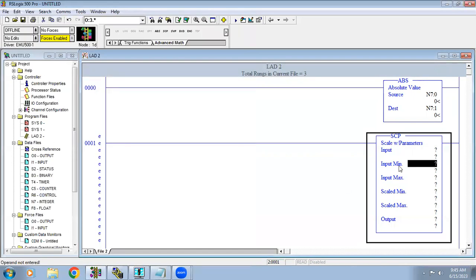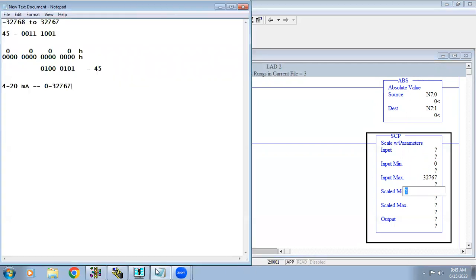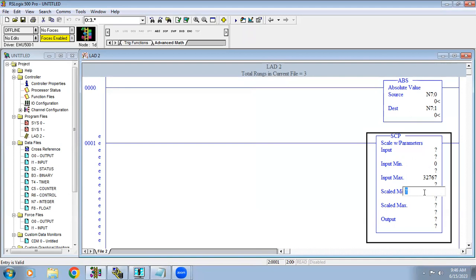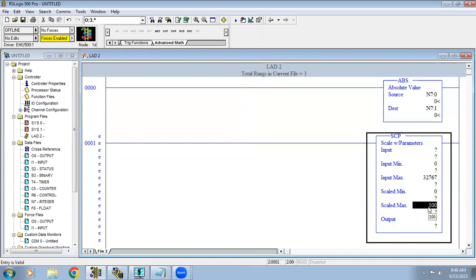So in the input minimum and maximum, the range we get is 0 to 32767. But I want to see the tank level in terms of 0 to 100 percent, not in raw resolution, because it is not easy to understand what level that value exactly represents. So in the Scale with Parameter block, you set input minimum/maximum as 0 to 32767 and scaled minimum 0, maximum 100.